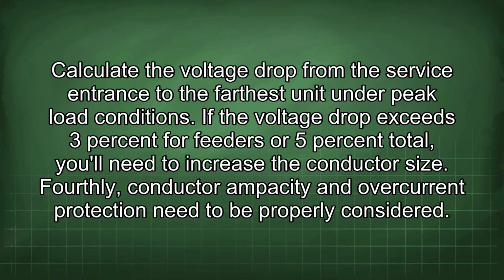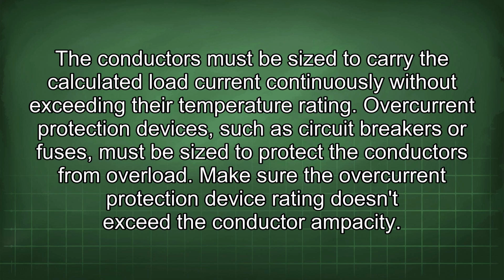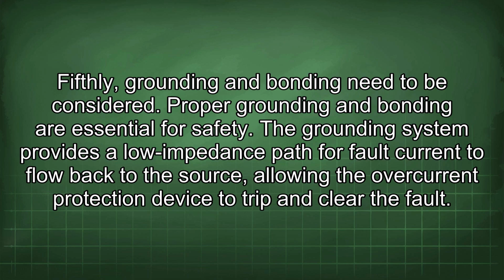Fourthly, conductor ampacity and overcurrent protection need to be properly considered. The conductors must be sized to carry the calculated load current continuously without exceeding their temperature rating. Overcurrent protection devices, such as circuit breakers or fuses, must be sized to protect the conductors from overload. Make sure the overcurrent protection device rating doesn't exceed the conductor ampacity. Fifthly, grounding and bonding need to be considered. Proper grounding and bonding are essential for safety. The grounding system provides a low impedance path for fault current to flow back to the source, allowing the overcurrent protection device to trip and clear the fault.